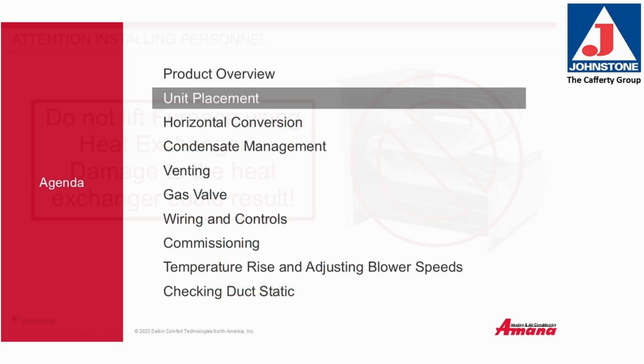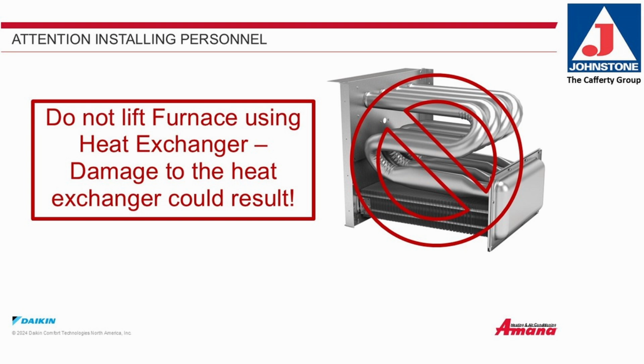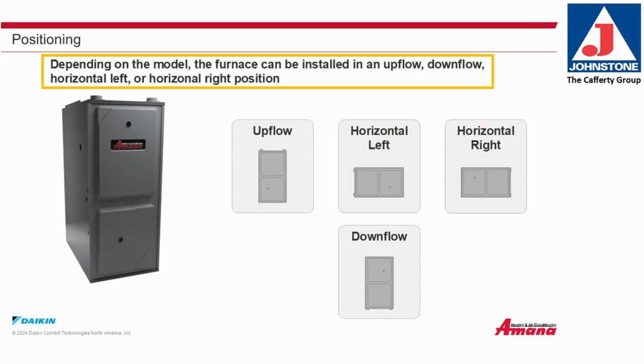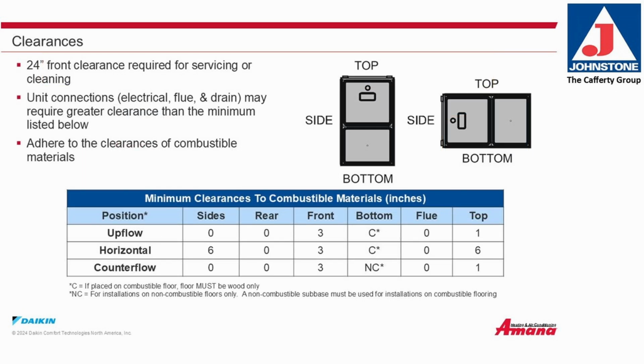Unit placement. Attention installing personnel. Do not lift the furnace using the heat exchanger. Damage to the heat exchanger could result. Positioning. Depending on the model, the furnace can be installed in an upflow, downflow, horizontal left, or horizontal right position. Unit cannot be installed on its back, nor can ductwork be attached to the back. Clearances. 24-inch front clearance required for servicing or cleaning. Unit connections, electrical, flue, and drain, may require greater clearance than the minimum listed below.